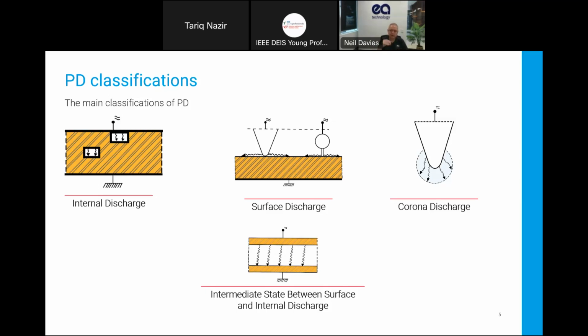The third main area is corona discharge. So that's from a sharp point into a gas, typically in air, often not a problem. So if we have that on an open terminal switchyard, then we're really not that particularly bothered about it. It might round off some edges, but all the gases that will be generated will dissipate, and it doesn't usually cause you too much of an issue.